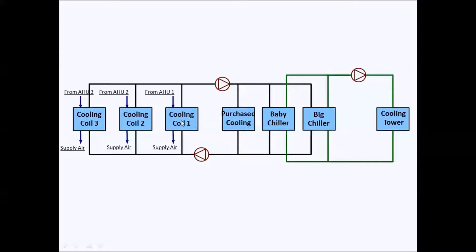Chilled water would be coming from three different sources: purchased cooling district cooling, small constant COP chiller we'll name baby chiller, and a big electric chiller named big chiller. These three would be providing chilled water to these three different AHUs. These two chillers, baby chiller and big chiller, a cooling tower will be connected to these two to serve as a condenser for these chillers.